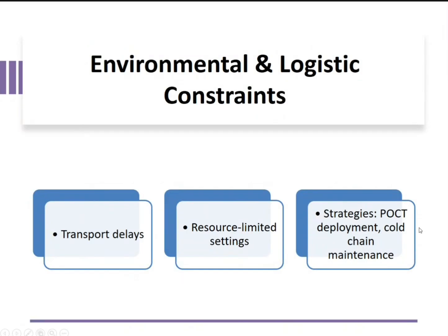So it's a point of care, and although it's point of care, that means it is not going to be positioned in the main central lab. The place of any point of care device is near the patient. So most of the ABG analyzers are going to be near the casualty or the ICU, where you have critical patients and you need ABG monitoring, right?